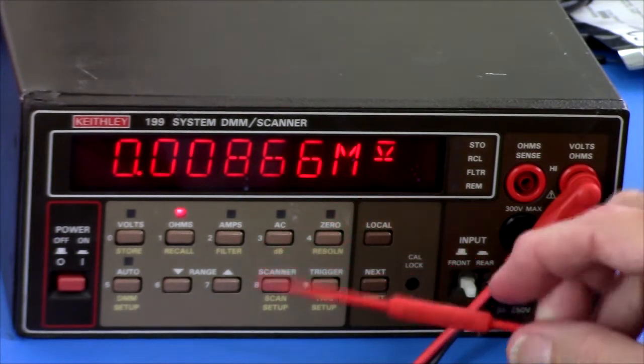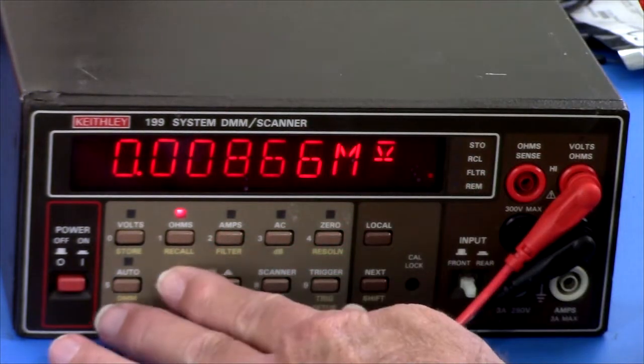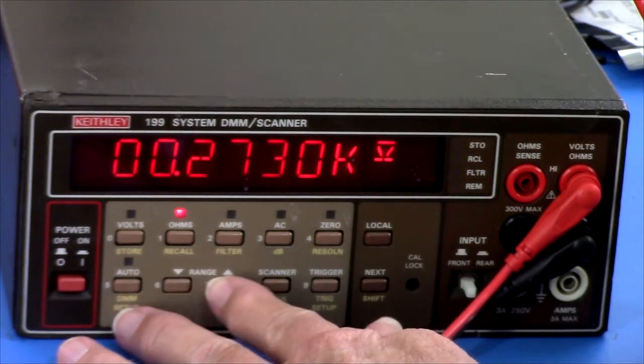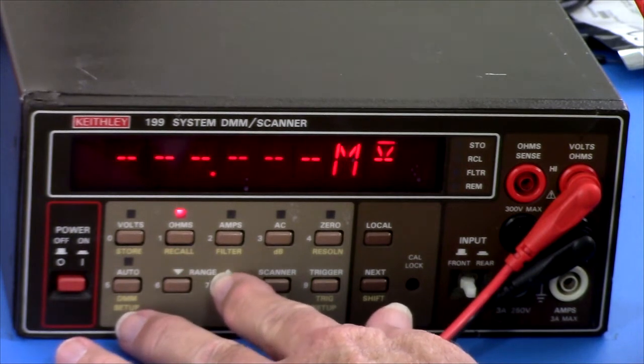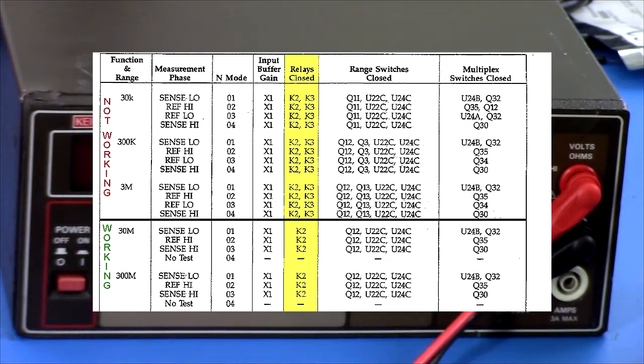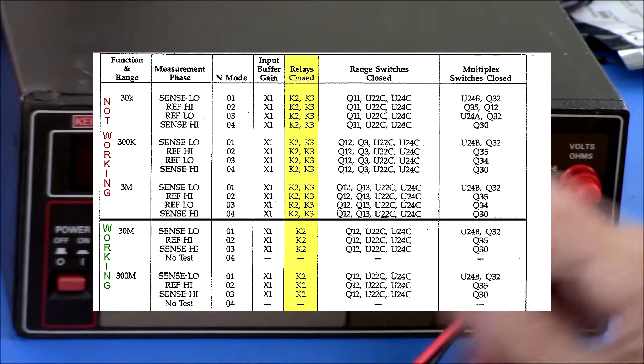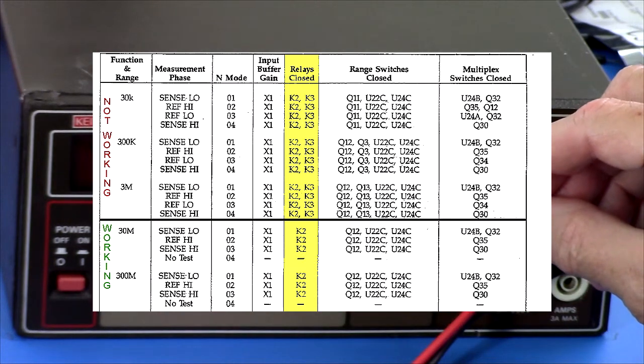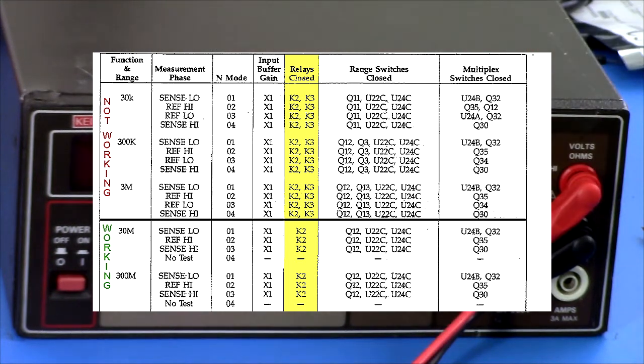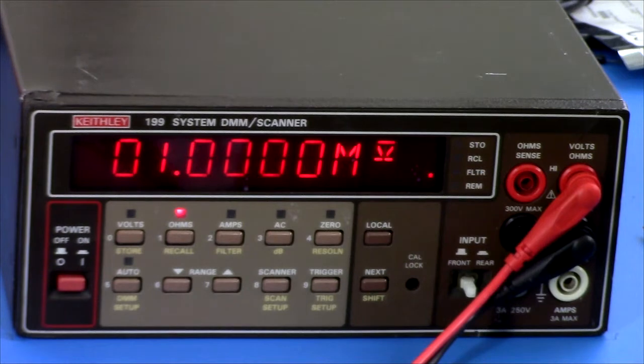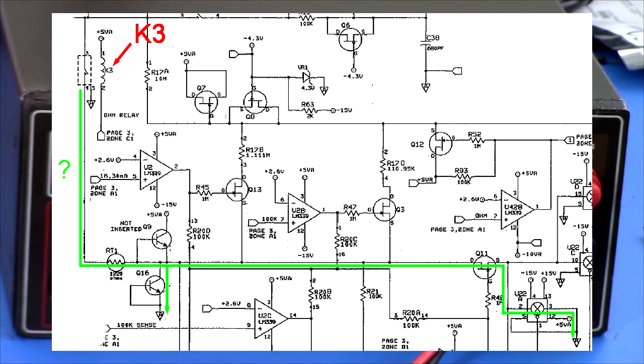And the difference between this scale, all the lower scales, right, and those top two is that relay K3 is engaged, is not engaged on the top two but is engaged on the lower ones. So the problem appears to lie somewhere after K3 in the circuit there.